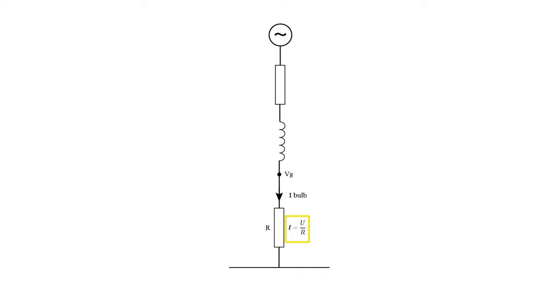Now consider that we are adding a linear load — a load that would normally not produce harmonics and would not normally be affected by harmonics. In the fourth picture, consider a light bulb added to our system next to the variable frequency drive. We can model this light bulb as a resistance — a simple resistor in parallel with the variable frequency drive. Since the current flowing to the resistor equals U divided by R (Ohm's law), if we have a distorted voltage we will also have a distorted current going into the light bulb.